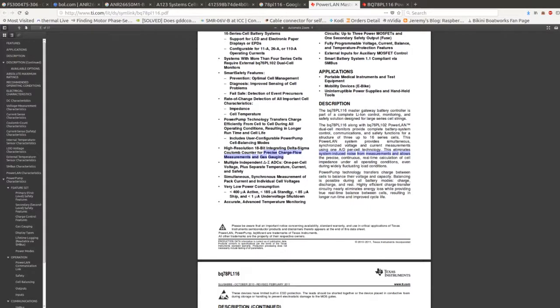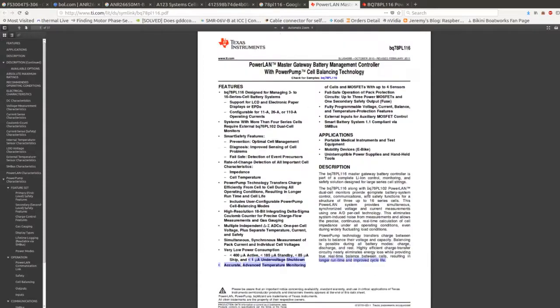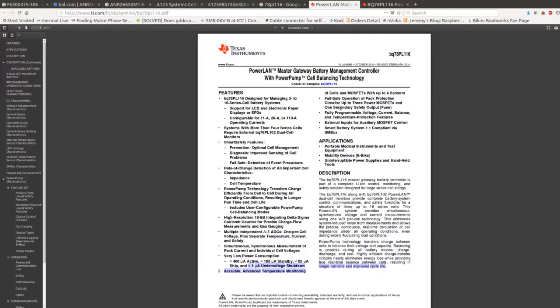It measures temperature, pack current, and individual cell voltage. 400 microamps active, 185 microamps standby, less than 85 microamps ship mode, and 1 microamp under voltage. That's good, because when your pack is under voltage, you don't want to be pulling a lot of charge to power your battery and your BMS. So this thing is smart enough to know it shouldn't be doing that and just pulls less than a microamp. That's good.